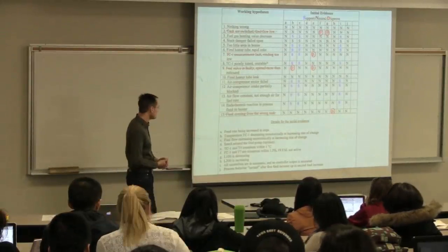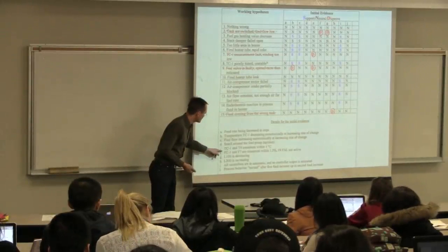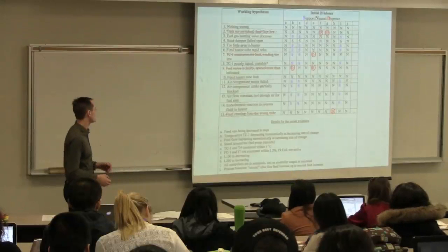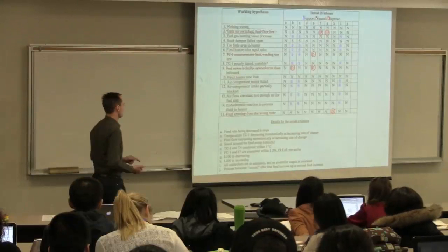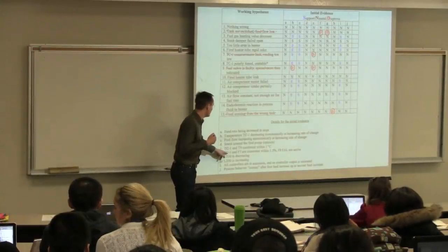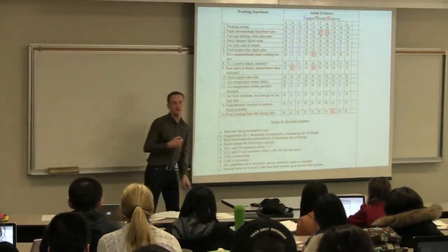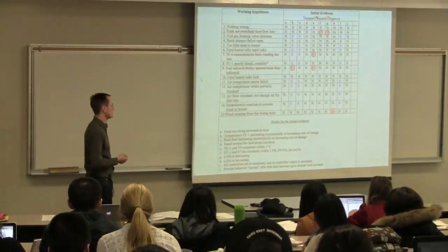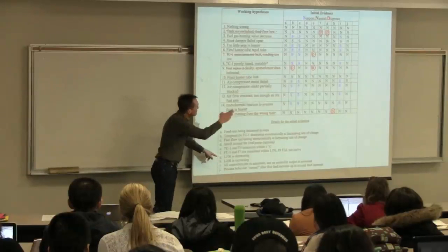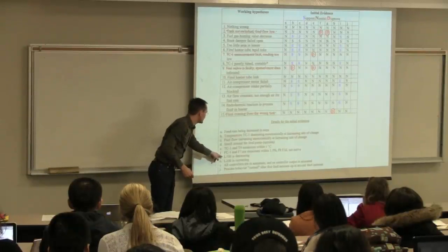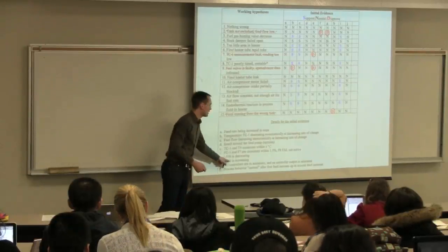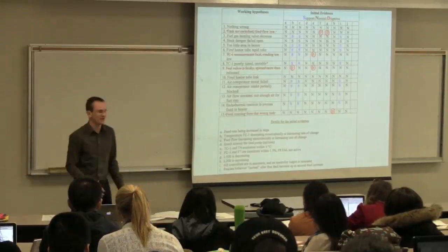Bearing that in mind, these next few points were the ones that we uncovered when we asked for some preliminary information. We checked preliminarily that TC1 and T4 are consistent with each other. That we did earlier on, and that the flow rate 1 coming into the fired heater and the flow rate 7 leaving at the end there are consistent with each other as well. And then G and H are the last two that we'll talk about before we go into this table, and that is that the level in the tank feeding the flow sheet is decreasing and L200 is increasing, the tank at the end.